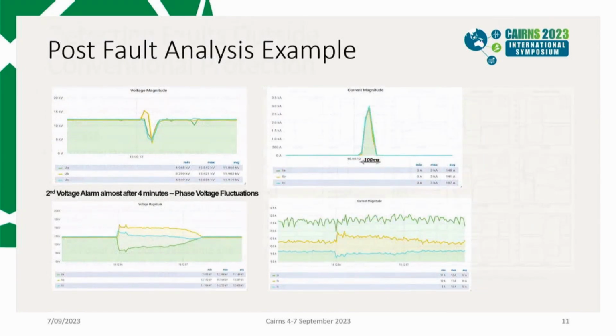When you have this sort of high resolution data being captured on your network all the time, it provides a wealth of information in post-fault analysis. Effectively, you've got samples being taken with GPS timestamps across your entire network, so the ripple effects of any major outages or any major faults, or even minor ones, could be seen all over the distribution network. And so it's an exciting time for this data implementation. As we're seeing improvements in our capability to manage large data sets, we'll start to see more and more of this technology rolled out. And in the future, we anticipate seeing more devices like PMUs integrated into recloser controllers as a common way to access this data and to harness the power of the data on your distribution network.